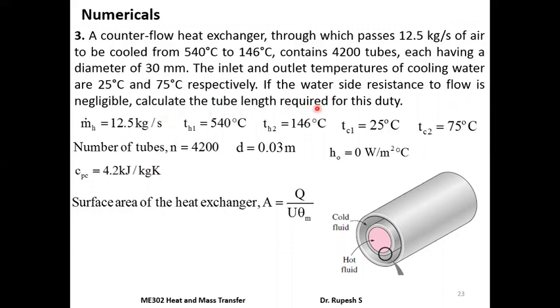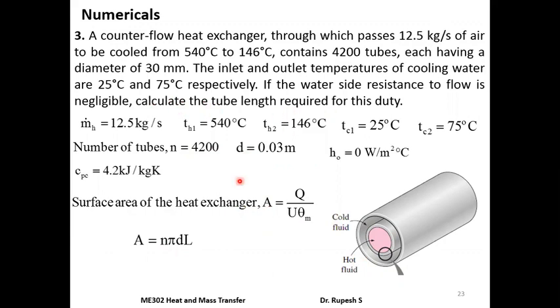Surface area A = q / (U × θm). The surface area is provided by the curved surface of the inner tubes. For a single tube, curved surface area = π × d × L. With n = 4200 tubes, total surface area = n × π × d × L. So once we find A, we can calculate length L = A / (n × π × d). We need to evaluate U and θm first.